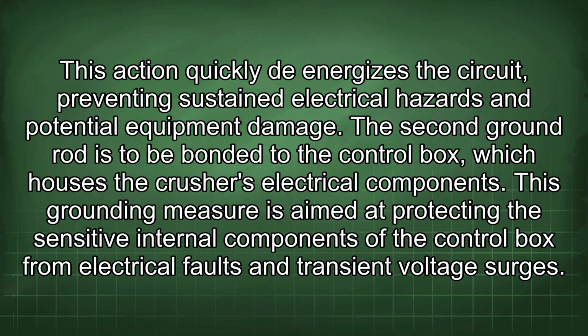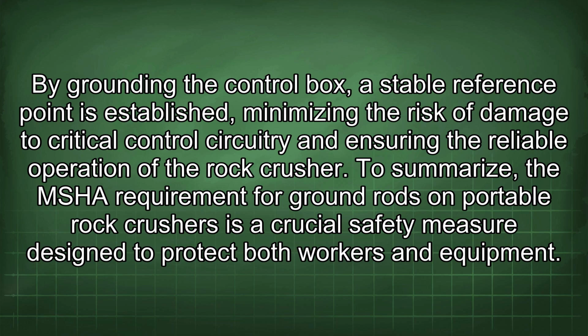The second ground rod is to be bonded to the control box, which houses the crusher's electrical components. This grounding measure is aimed at protecting the sensitive internal components of the control box from electrical faults and transient voltage surges. By grounding the control box, a stable reference point is established, minimizing the risk of damage to critical control circuitry and ensuring the reliable operation of the rock crusher.